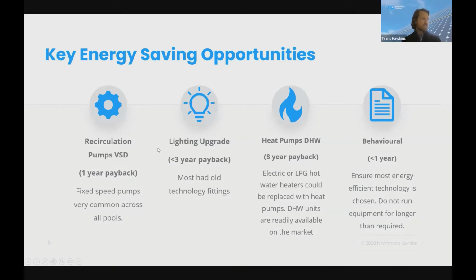One is dealing with recirculation pumps running through filtration systems. It's quite common to find pumps running at fixed speeds with flow rates throttled by a manually operated valve, which is a very inefficient way to reduce flow. It's better to install a variable speed drive to directly control the pump's output according to the level of circulation needed.